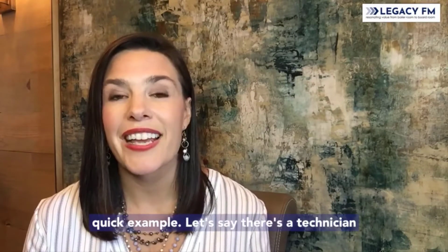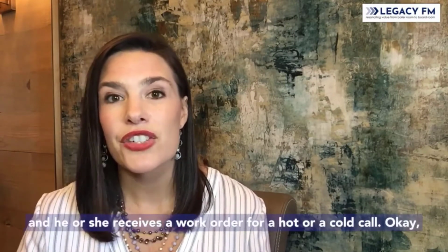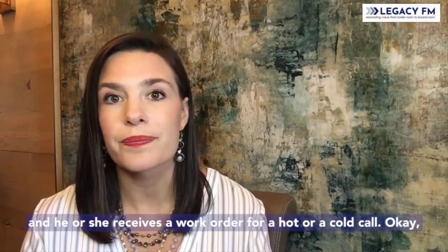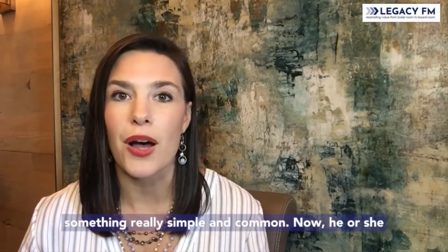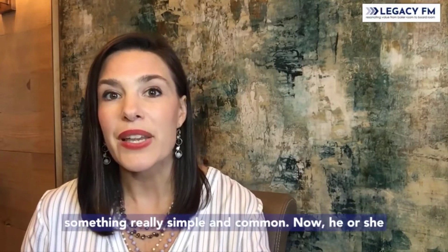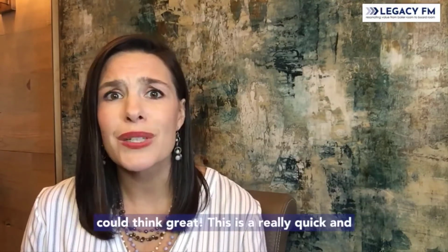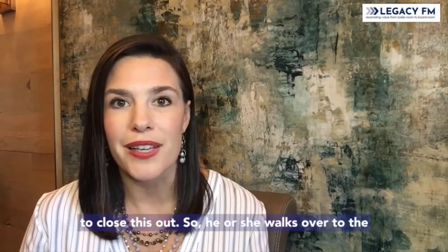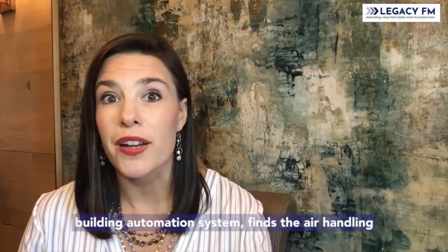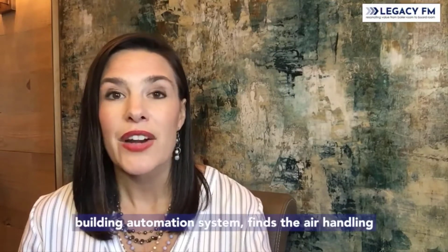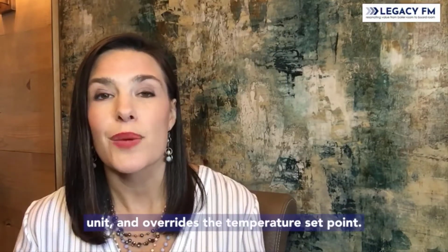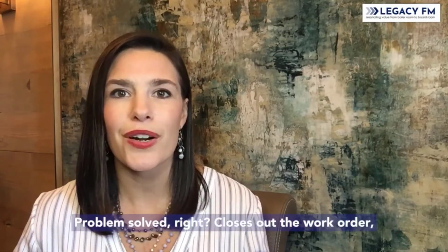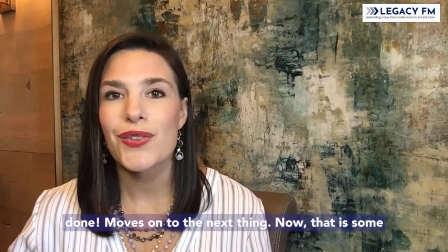Let's say there's a technician and he or she receives a work order for a hot or a cold call. Okay, something really simple and common. Now he or she could think, great, this is a really quick and easy work order. It's going to take me 2 minutes to close this out. So he or she walks over to the building automation system, finds the air handling unit, and overrides the temperature set point. Problem solved, right? Closes out the work order, done, moves on to the next thing.